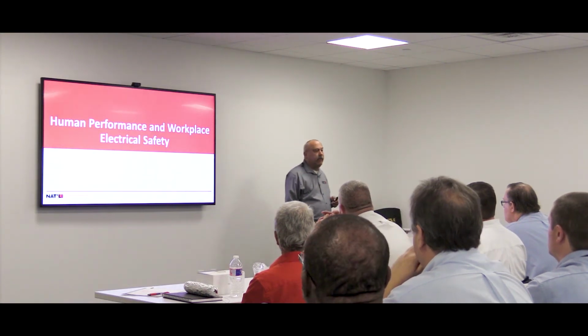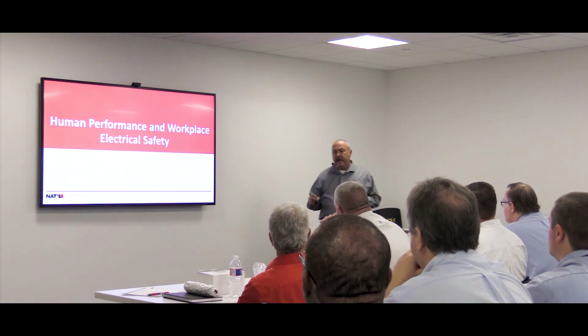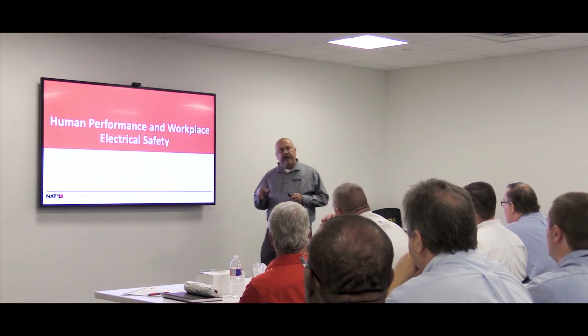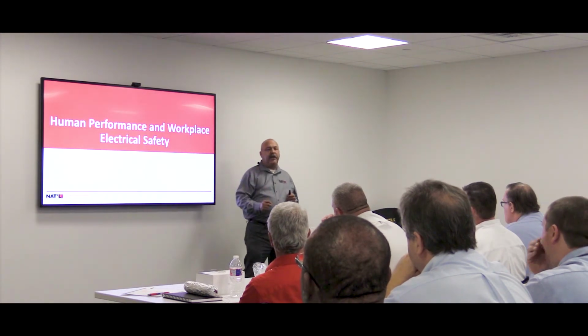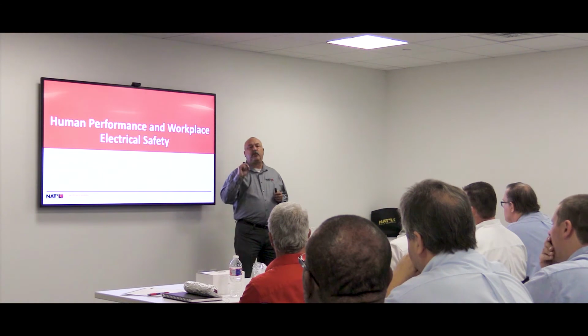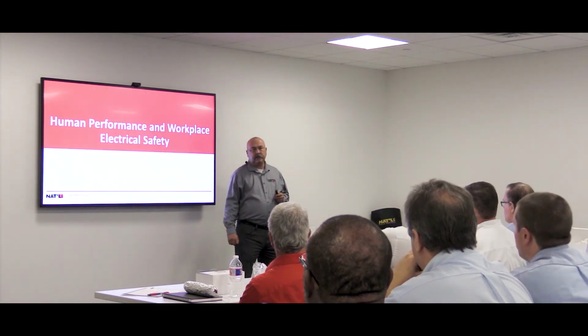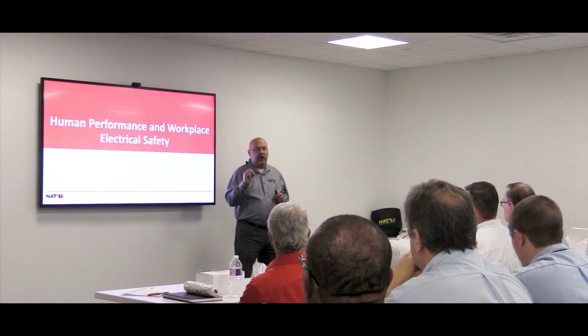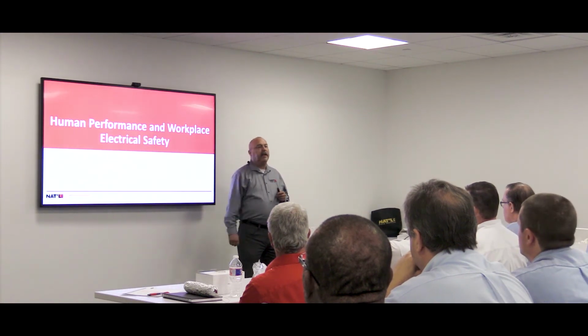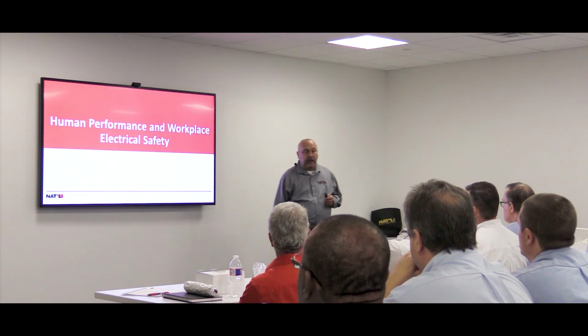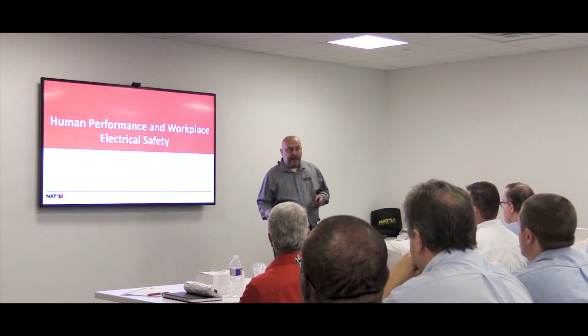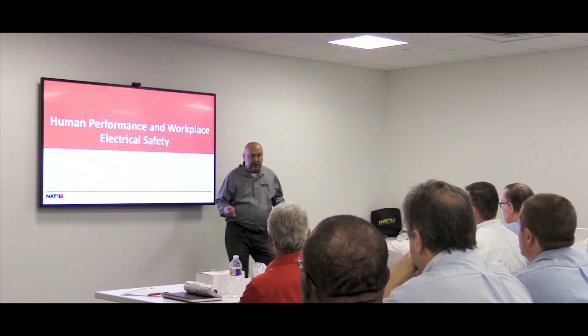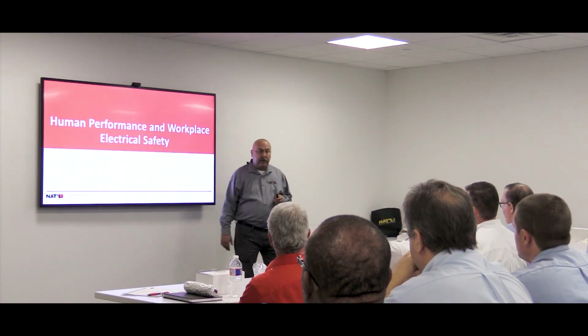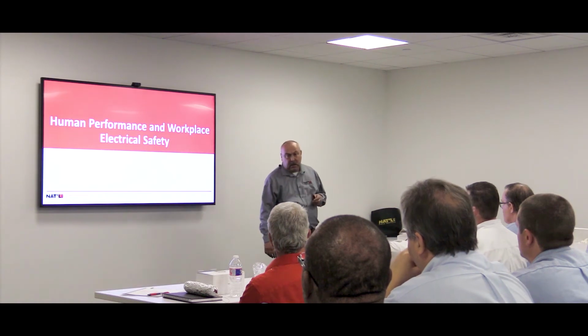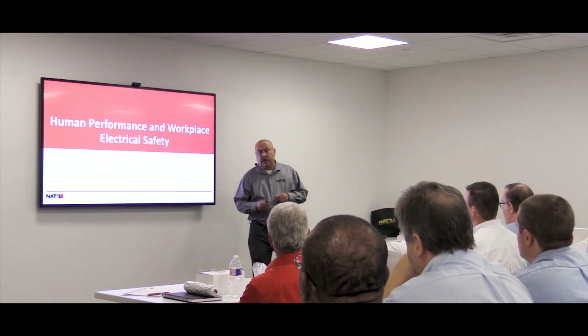OSHA has clearly, in several cases, already stated that the interruption of production or inconvenience is not justification for doing energized work. That's crystal clear in their documentation. That's not a reason. It has to be a greater risk, and greater risk they narrowly define, or it has to be infeasibility. That's where your IR comes in. And then they expect you, if you're doing infrared on your buildings, if you can put windows and windows will work, to have windows. Now, windows don't work on a lot of things we do, so we still got to pull covers off. But here's the part about this when they added the human performance.